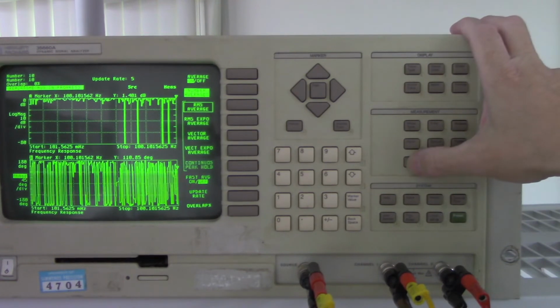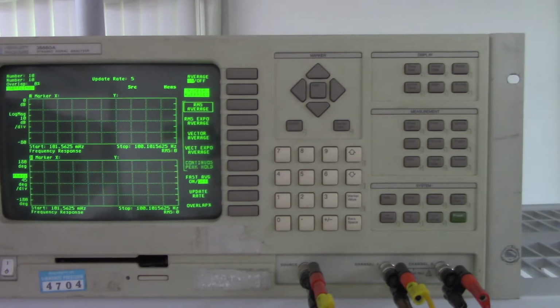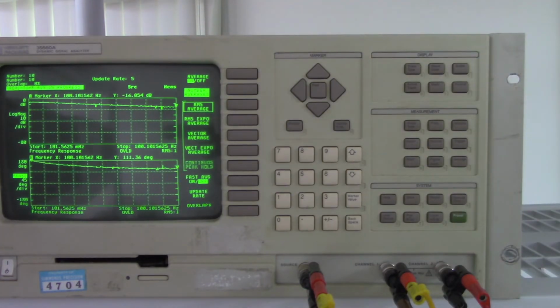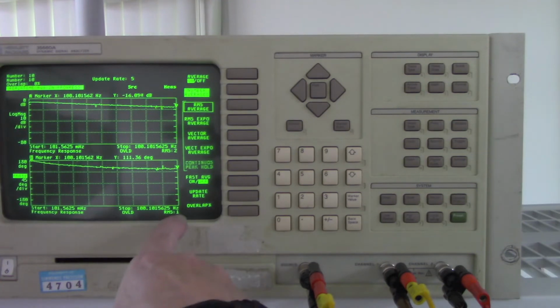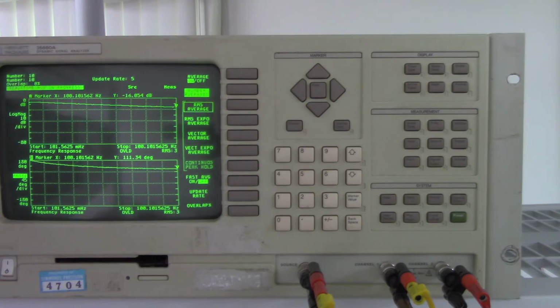So I'm going to hit start here, and hopefully it will start this frequency response and average it over 10 times. So it says real time averaging in progress. So it did the first average.